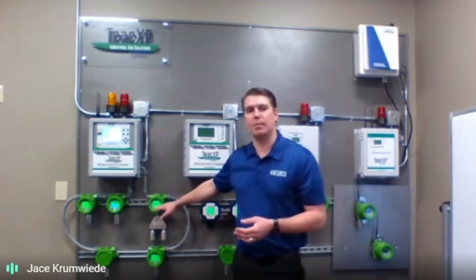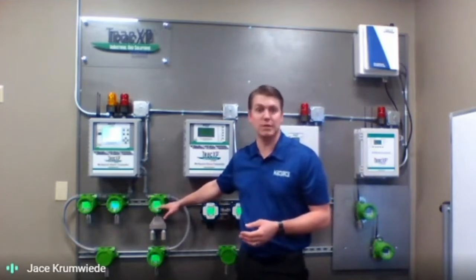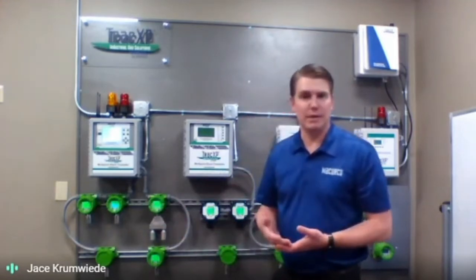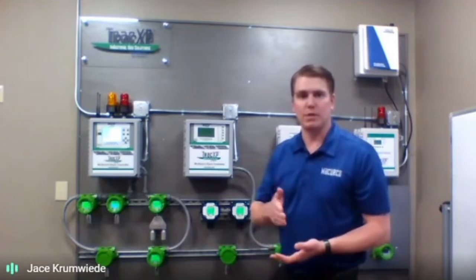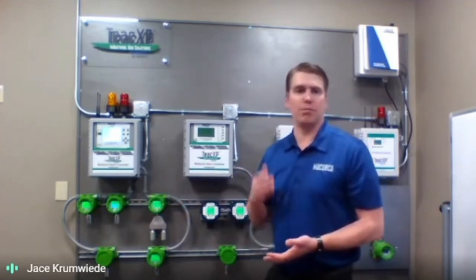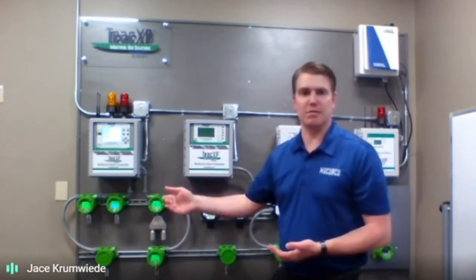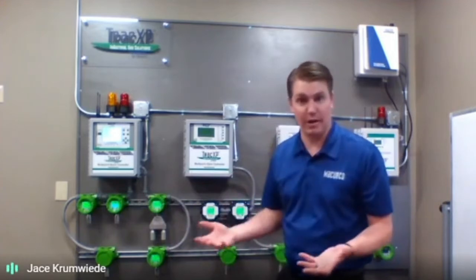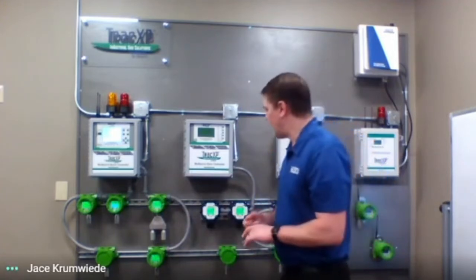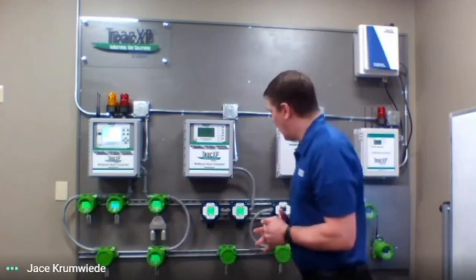The T40 is our flagship. It does have a color backlit display, so green is good. When you're not seeing any dangers, it's going to be green. When it goes into individual alarms, you'll go from yellow to orange to red, progressively indicating the severity of said alarm. So very easy to see from a distance, very handy.